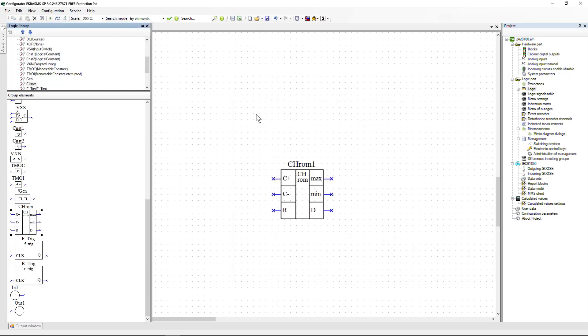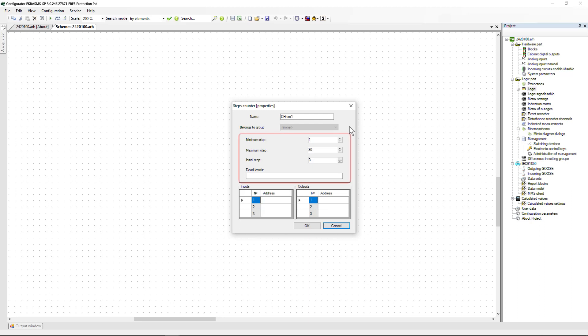Counter of OLTC drive steps (On-Load Tap Changing): a logic element designed to determine the number of the current step and issue signals when reaching the highest or smallest OLTC steps. It is possible to determine dead steps. Signals Add, Reduce, and Reset are assigned to the input. The Reset signal sets the counter value equal to the initial step. At the output, signals Maximum Step, Minimum Step, and Dead Step are generated. Settings specify the maximum and minimum steps, the initial step, and the numbers of dead steps.